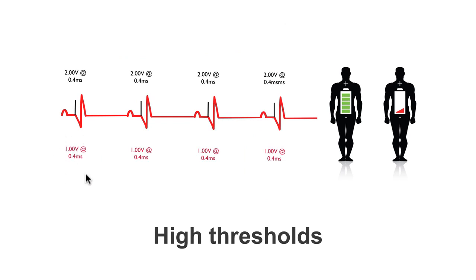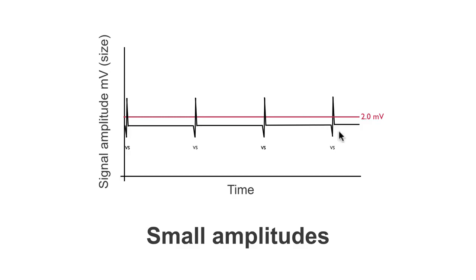Now, quite often by making that small change, we can go back and look at our values again. In this patient, their threshold has returned to a nice one volt at 0.4 milliseconds. This enables us to put the output pulse at two volts at 0.4 milliseconds, and still maintain safe function of the pacemaker without the additional drain on the battery. Two volts at 0.4 milliseconds is a very normal output pulse for a pacemaker, and so this person will have good longevity from their device. We can also see that the amplitude size has improved — before we were just marginally over two millivolts, and now the ventricular signals are much greater than the two millivolts that the ventricular sensitivity is set to. This will put your mind at rest that the pacemaker will continue to function normally.